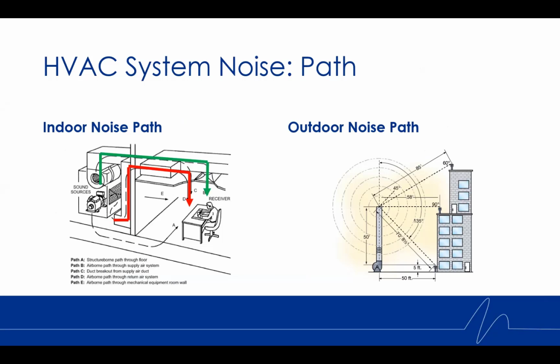Let's move on and take a look at the path here. On the left, we have an indoor noise path. Like I've already explained, we have a piece of equipment, and this one's inside a mechanical room. We have the air traveling from the fan inside the unit through the ductwork to the receiver that's sitting in the room. Same thing can be said for the return path. That same sound is going to be traveling through the return ductwork into the room where the person is sitting. The reason that path becomes important here is because as that noise travels through the ductwork, it's going to experience elbows. It travels through long runs of duct. There are transitions, and there's expansion and contraction of the air itself as it's traveling. All these things tend to naturally attenuate or absorb some of the noise that's in the airstream. So generally what the receiver is hearing in the space is going to be a little bit less than what's actually being expressed by the fan itself.